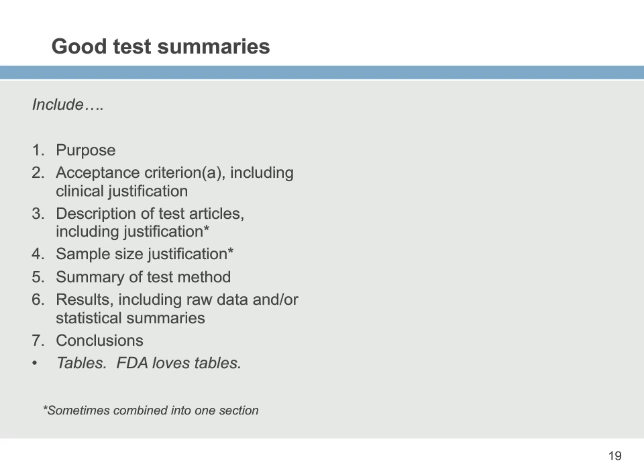So what doesn't it include? Here are the things that, you might think, oh, FDA, they're in the test report, and they should be, but they don't really need to be in a test summary. You don't want to start off by saying, oh, by the way, this was done in compliance with design control. I mean, it should be done in compliance with design control, but simply saying it's in compliance with design control doesn't demonstrate that the product is safe or that it's effective. Likewise, things like location and date of the testing and the report, or who's doing the testing, are important things to have in your test report because that's part of traceability and responsibility. But really, FDA doesn't care a whole lot about who does the test. It could be done by a third party. It could have been done 10 years ago. But if it's relevant, it still matters, and that's what you want to talk about. You want to talk about the data and its interpretation.